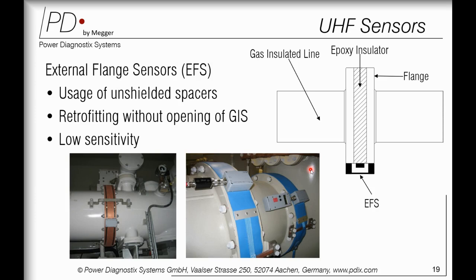But let's take an example: you have some old GIS and you want to do partial discharge measurement, right? Because without PD, you have no idea what's happening in your GIS. So you have an option to connect external sensors on the GIS. Technically, when you don't have any inbuilt UHF sensors, you completely depend on the design of the GIS. If you have spacers present where two enclosures are connected, it's typically unshielded spacers. Retrofitting can be done without opening the GIS, of course, but it is not as good as the inbuilt UHF sensors.